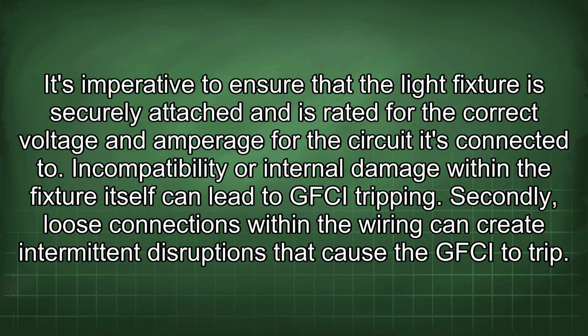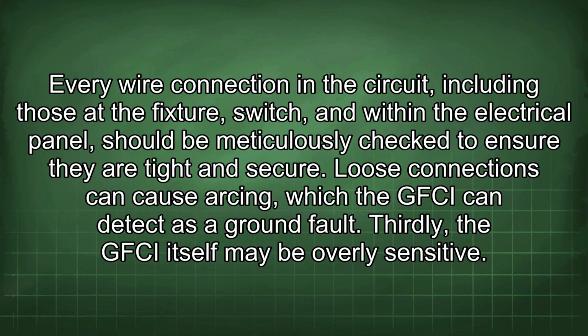Secondly, loose connections within the wiring can create intermittent disruptions that cause the GFCI to trip. Every wire connection in the circuit, including those at the fixture, switch, and within the electrical panel, should be meticulously checked to ensure they are tight and secure. Loose connections can cause arcing, which the GFCI can detect as a ground fault.